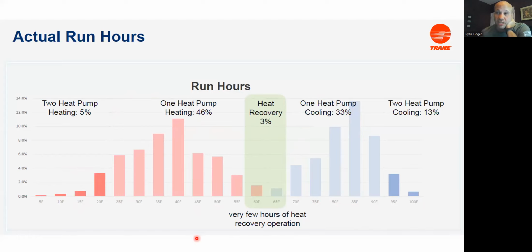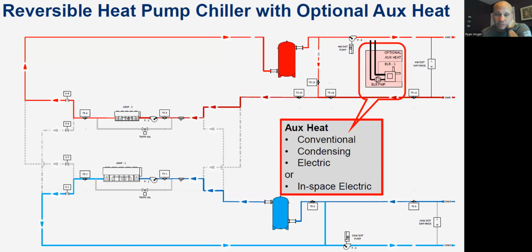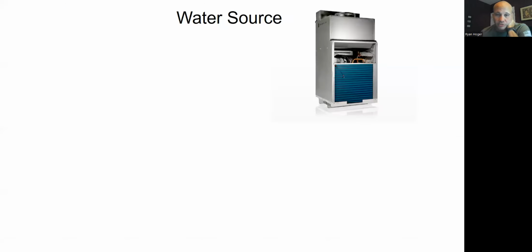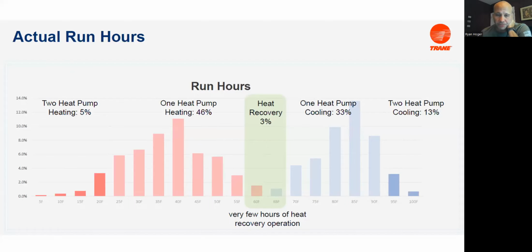So some buildings need a lot of heat recovery. Remember I said, if you have a lot of domestic water, like hotels, laundry, showering, condo buildings, swimming pools, those kinds of things. Then there are other buildings, like an office building, where you don't have a lot of time that I need both simultaneously. There is some, but it becomes less interesting because you don't use a lot of domestic water in an office building. So in that case, it might be smarter to have these two machines piped like this, where they can both run heating or both run cooling. So there's a lot of variables on what we can do with all these chillers.